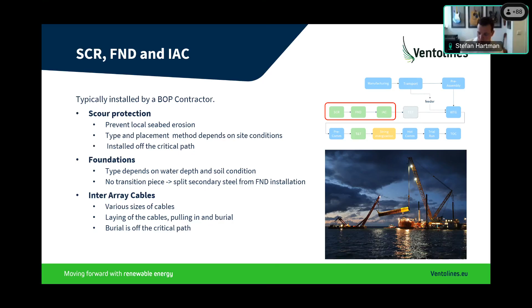When the foundations are there, in parallel you need an offshore high voltage station as well - not shown here in the picture, but that's a parallel scope. You have the offshore high voltage substation, and then you connect it with array cables. The closer you are from the daisy string of turbines to the offshore high voltage substation, the bigger the cables are, because there's more current going through them. Installation of the cables is typically on the critical path, but the burial can be done off the critical path.